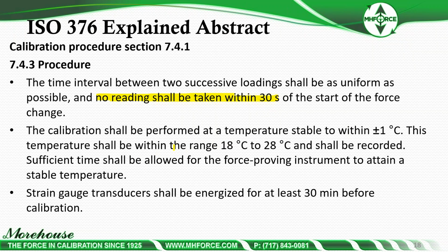Sufficient time shall be allowed for the force proving instrument to attain stable temperature. That's typically on the end user; the mass of the material and everything else will determine how long an instrument needs to acclimate to room temperature. Strain gauge transducers shall be energized for at least 30 minutes before calibration. This is good practice anyway, to warm up the equipment, to get the signal, if you're using 5 volts or 10 volts excitation, to get everything warm and electrically stabilized.